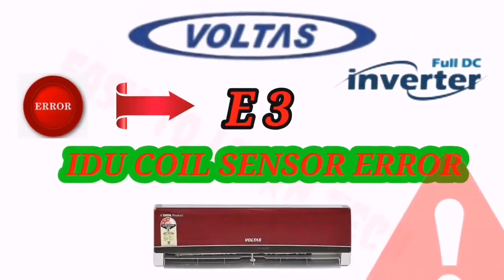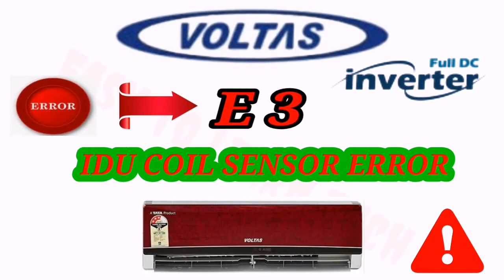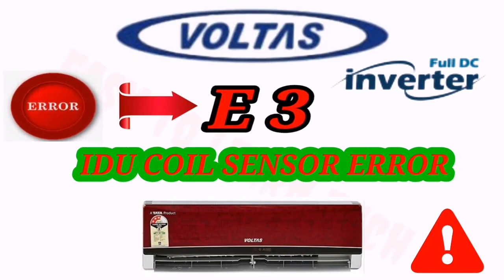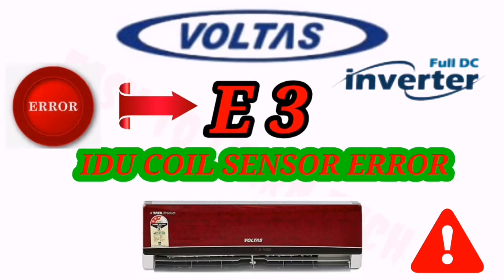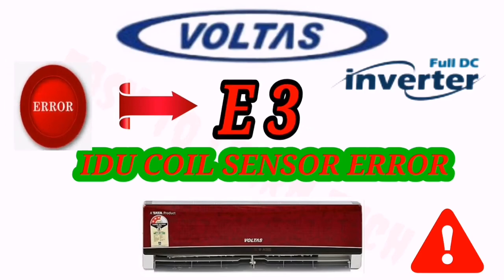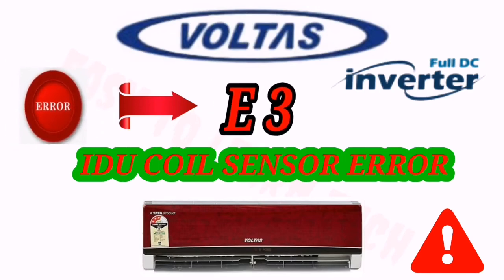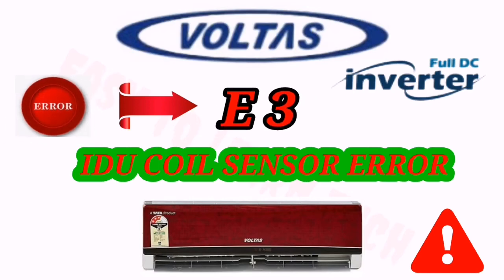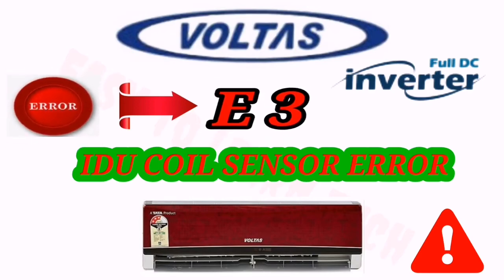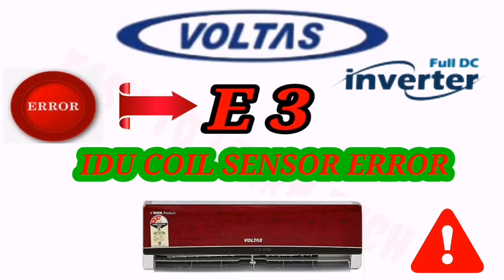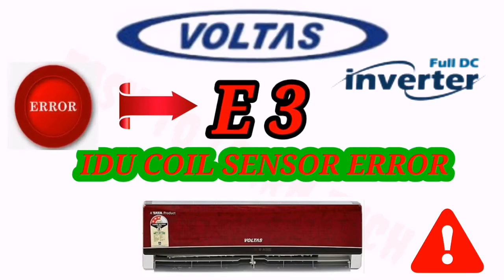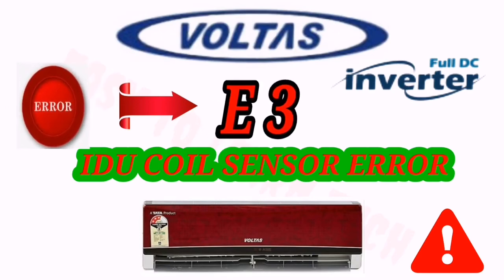Let's see the next error code. When you see E3 in your display, it means indoor coil sensor error. Indoor coil sensor error is the same as the indoor room sensor error. You have to follow the same steps and check all of them step by step. You have to check the placement, the connection, the resistance, and the power supply from the PCB. And our unit will be in working condition.